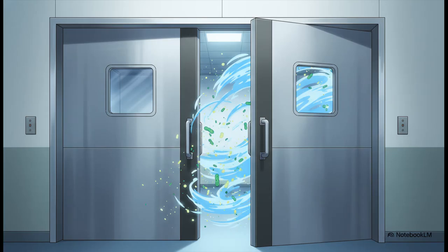And get this, here's a really surprising fact about those heavy doors. Even though the rooms are equipped with double-acting swinging doors that have rubberized guards and little windows, using them is heavily restricted. Our source notes that the physical action of swinging a door produces air turbulence. That turbulence kicks up microscopic particles, instantly increasing the bacteria count in the air. So, during a procedure, movement through those doors is kept to an absolute minimum.